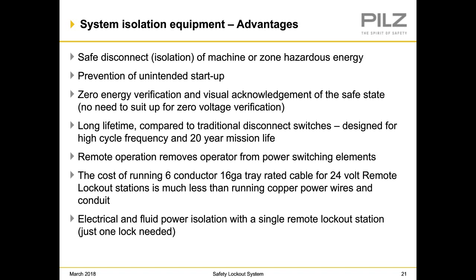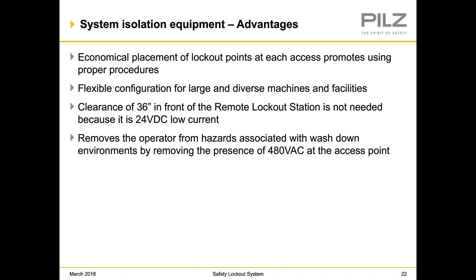Electrical and fluid power isolation with a single remote lockout station, so just one lock needed to do electrical as well as the fluid power isolation. Also, economical placement of lockout points at each access location promotes using proper procedures. As well, flexible configuration for large and diverse machines and facilities. Clearance of 36 inches in front of the remote lockout station is not needed because, again, it's only 24 volts, low current. Also, this removes the operator from hazards associated with washdown environments by removing the presence of 480 volts at the access point.